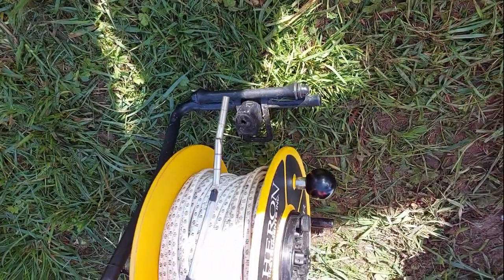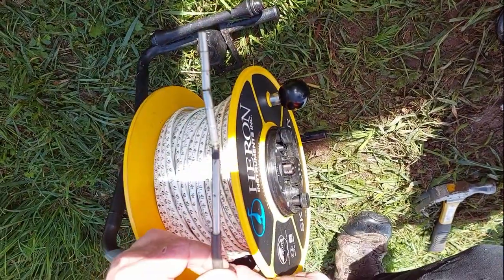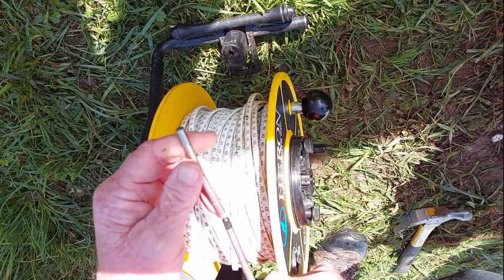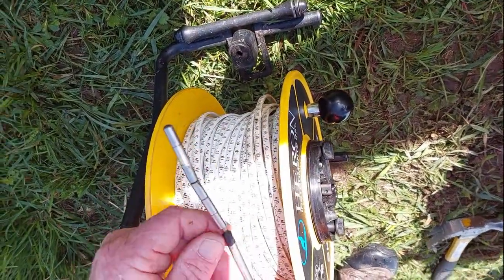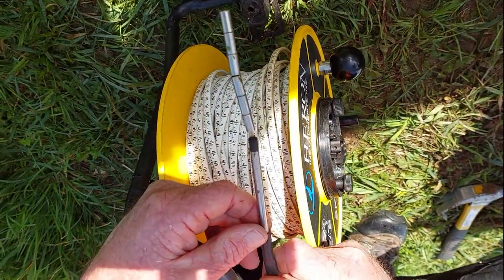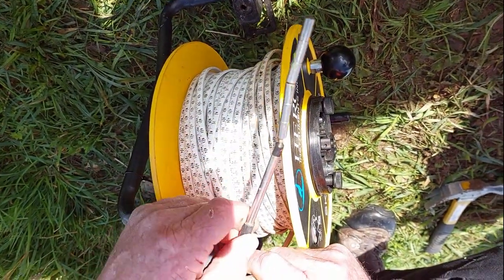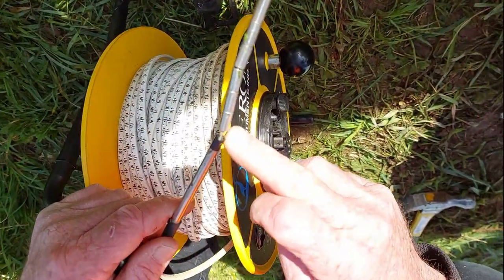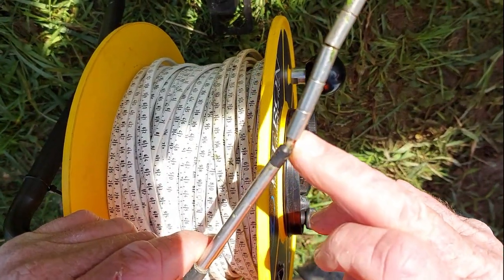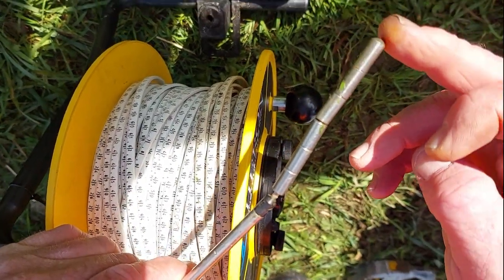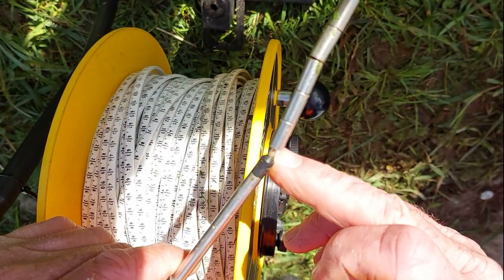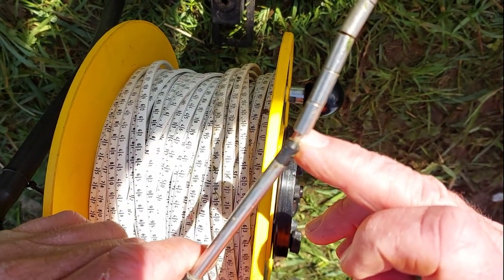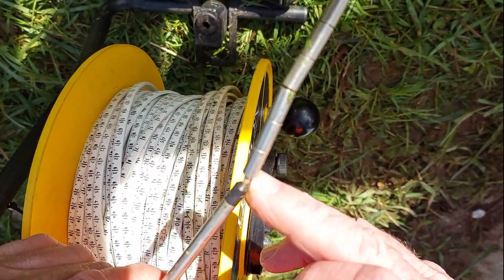So this is a Heron skinny dipper. It sort of speaks for itself. It's got a narrow probe which is more suitable for your piezos that are quite narrow in diameter. The measuring point for this probe is right here. So unlike some of the others that have their measuring point at the bottom of the probe, this one is mounted partially along the body.